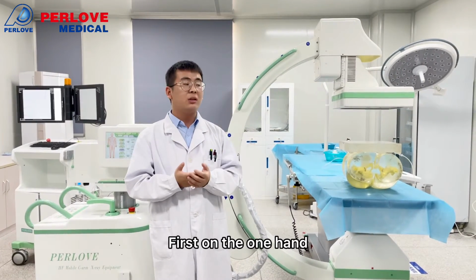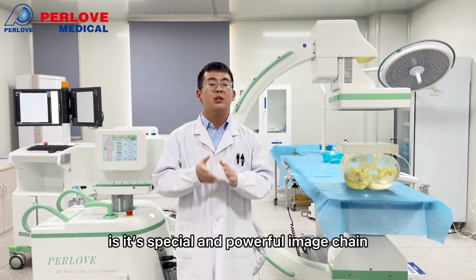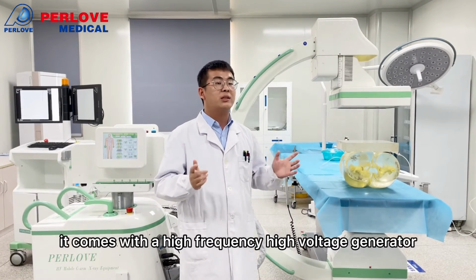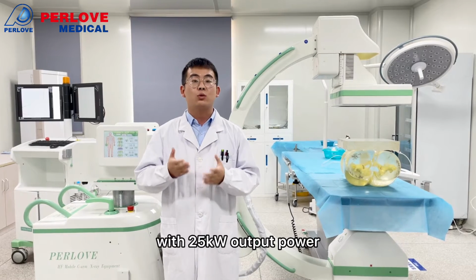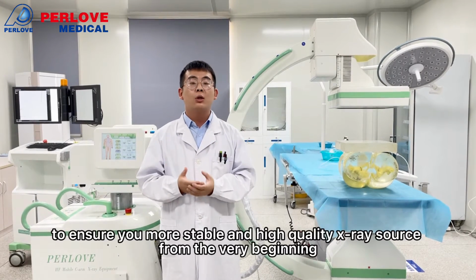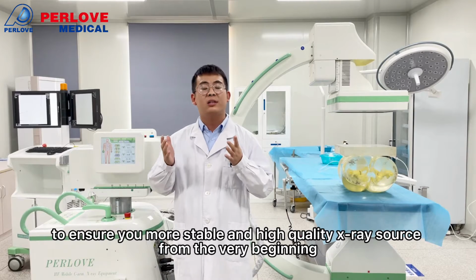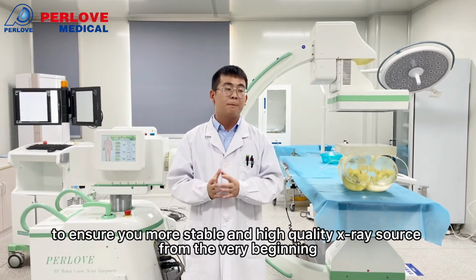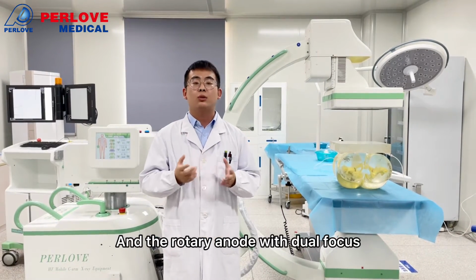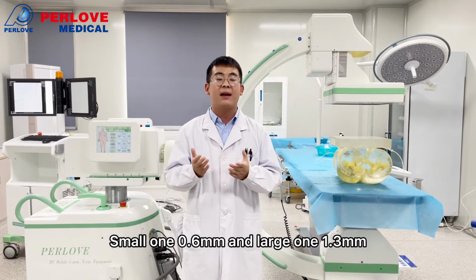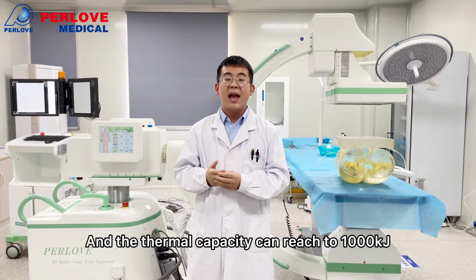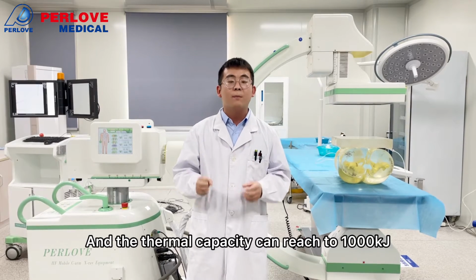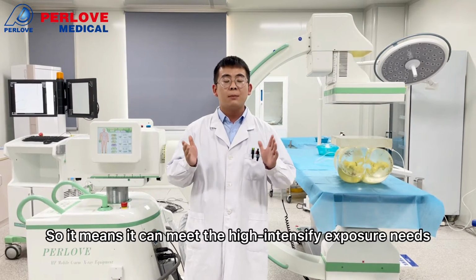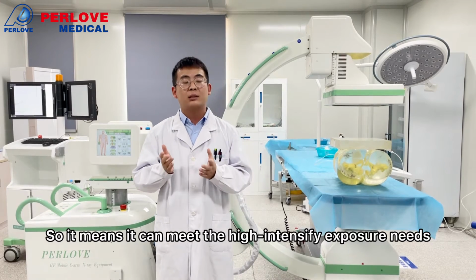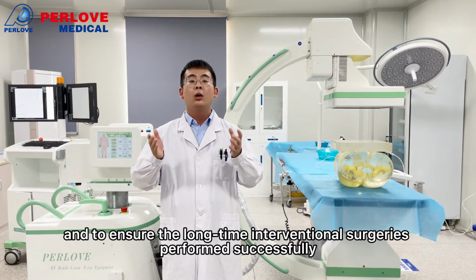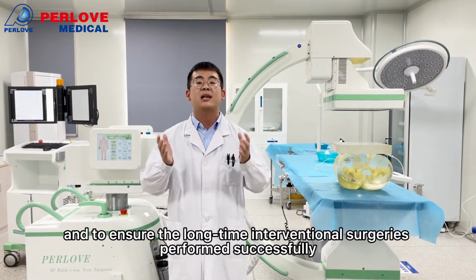First, on the one hand, is the powerful image chain. This machine comes with a high-frequency, high-voltage generator with 25 kW output power to ensure a more stable and high-quality X-ray source from the very beginning. The rotary anode has a dual focus, a small one of 0.6 and a larger one of 1.3 millimeters. The thermal capacity can reach 1000 kilojoules, so it can meet high-intensity exposure needs and ensure long-time interventional surgeries are performed successfully.